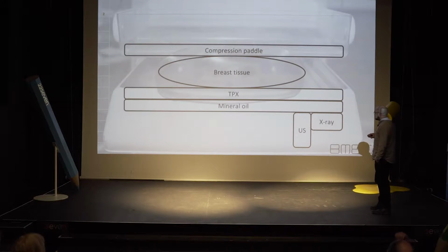Humans can hear sounds with frequencies up to 20 kilohertz, but medical ultrasound uses frequencies about 100 times greater than that. And unlike audible sound, it doesn't travel through air. So that was our first challenge, to find a way to connect the ultrasound probe to the breast using a combination of liquids and solids. And that's called acoustic coupling. We solved the acoustic coupling with the mineral oil and the TPX. Why and how we did that is a topic best suited to a series of lectures.